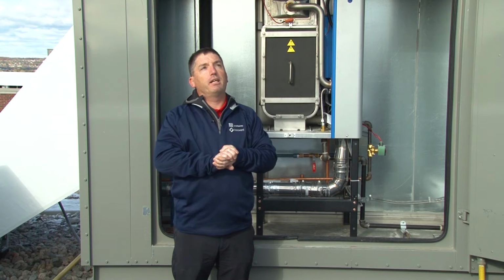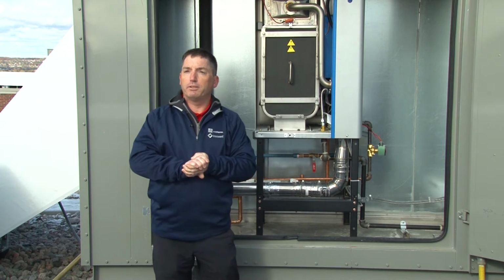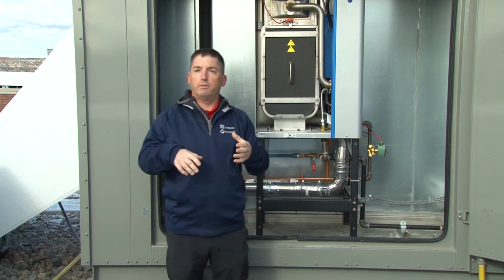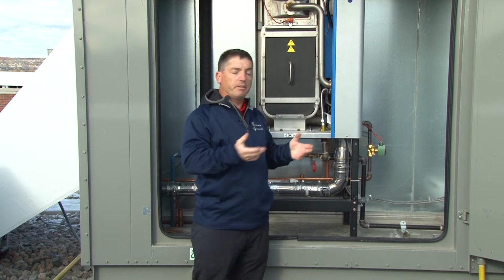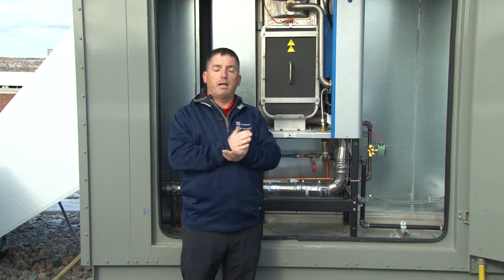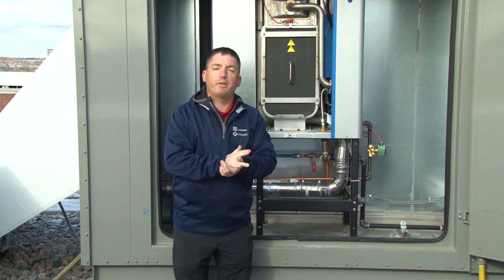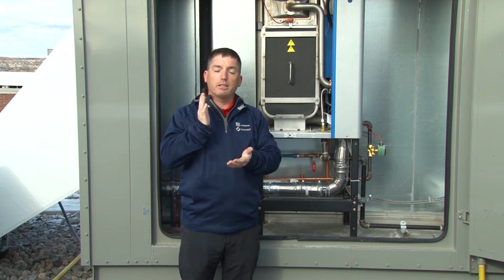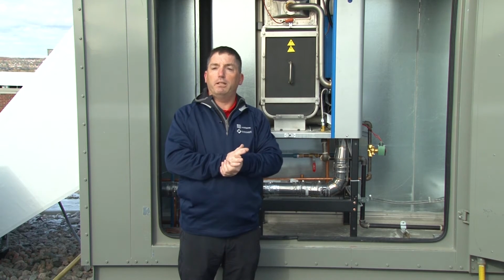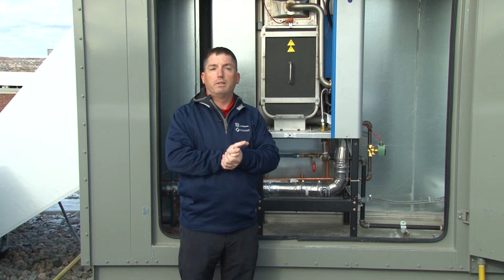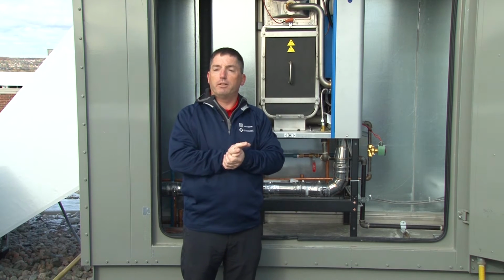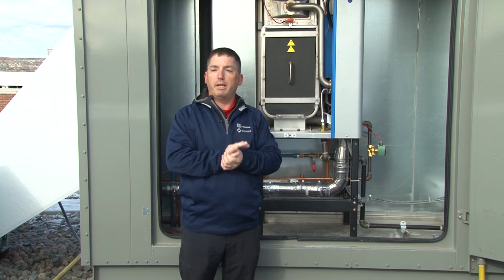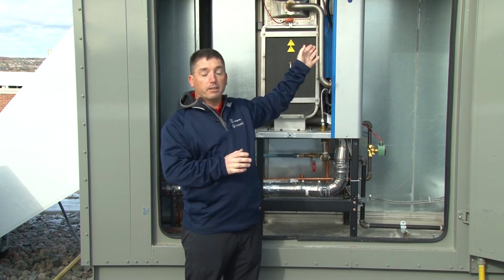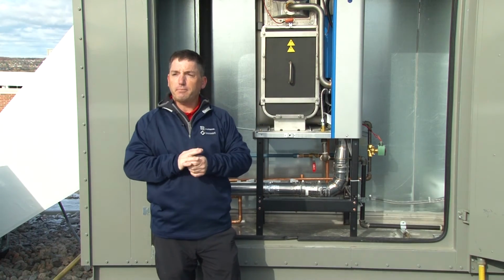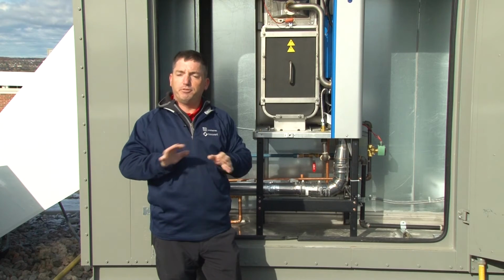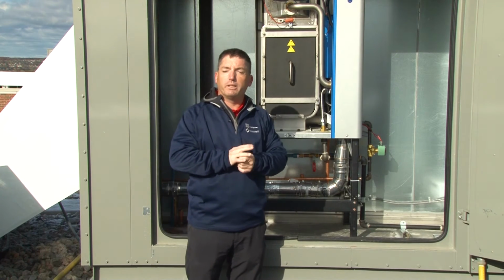I believe we'll call it a light maintenance, where you're basically just going to check, make sure everything looks okay. And then after, I believe, 2,000 hours, it's actually going to shut down completely, and it won't allow the unit to run until you've done what they consider to be a major service. And again, it's all going to be identified in full text right on the Nortec keypad.